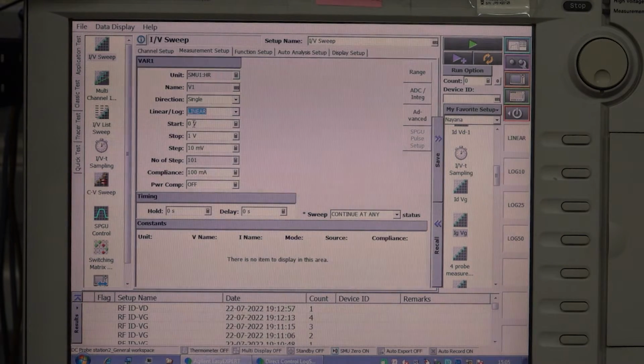The start voltage, according to the measurement requirement, we can enter here. Suppose I use a solar cell, I can give -1 to +1. The step voltage of 20 millivolt I have given. So now my number of steps is 101. A standard measurement setup will have 101 steps. This is for better accuracy of the data.